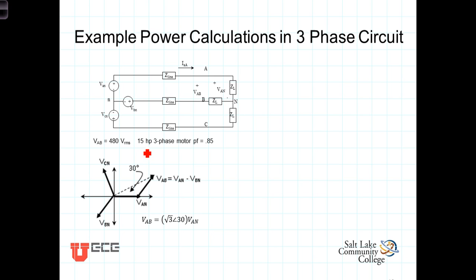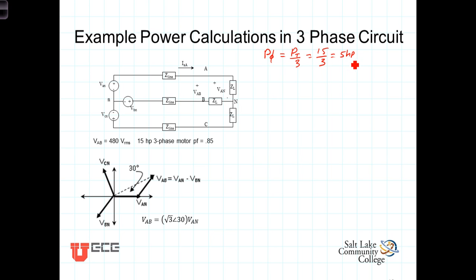In this case, we've got a Y-connected load. We're told that it's a 15-horsepower three-phase motor with a power factor of 0.85. That 15-horsepower is the total power — the rating on a motor is the total power you can get out of the shaft. Because it's a three-phase motor, a third of that power will come from each phase. So the power per phase equals the total power divided by three, which is 15 divided by 3, giving us 5 horsepower per phase, which converts to 3,730 watts per phase.